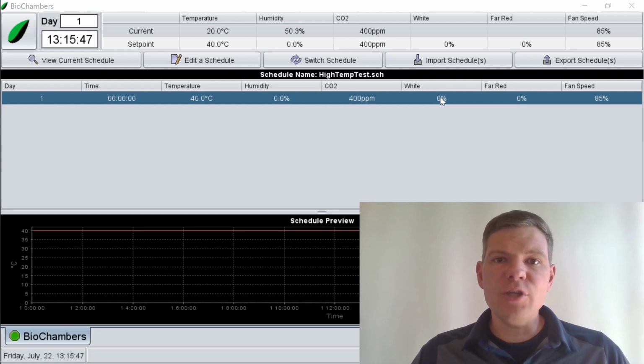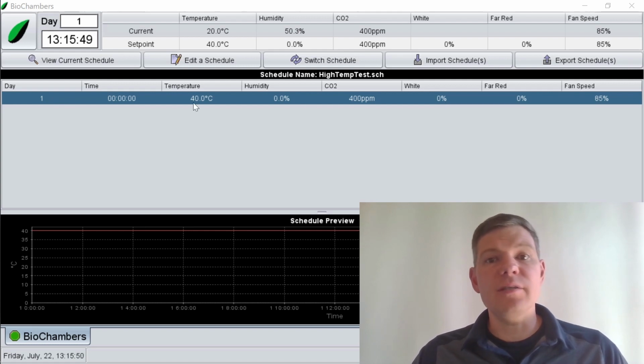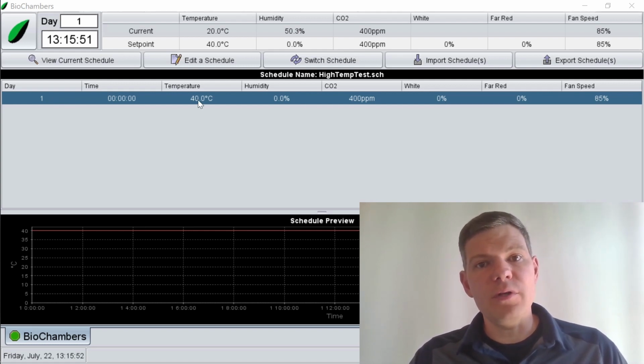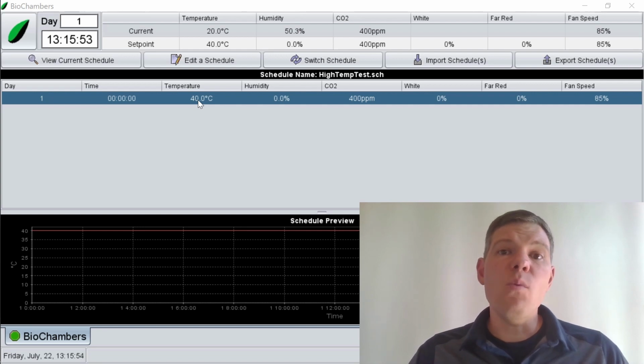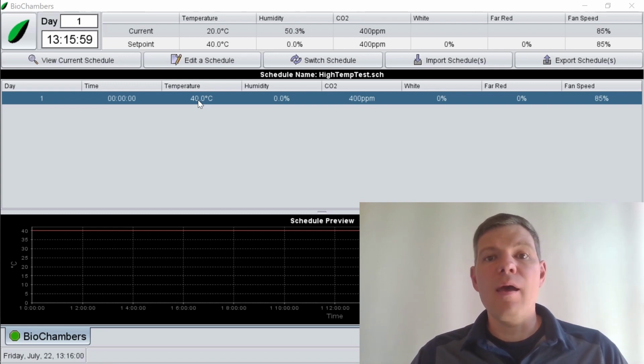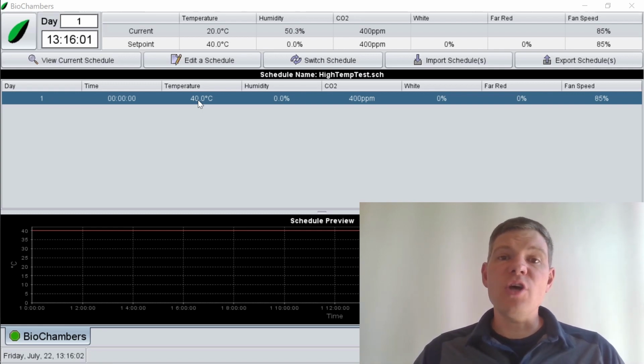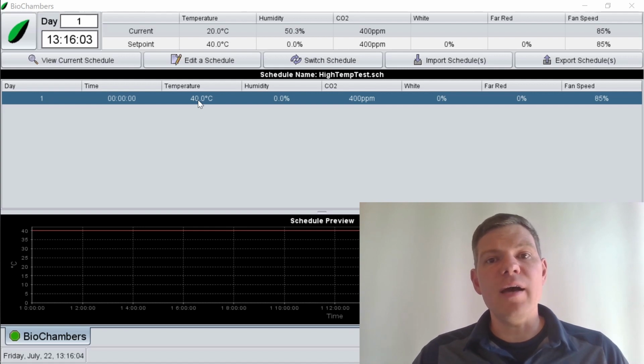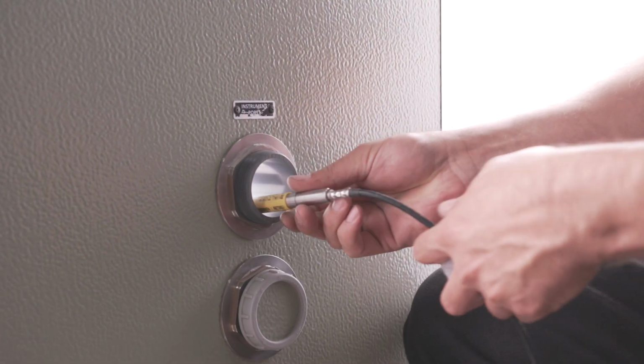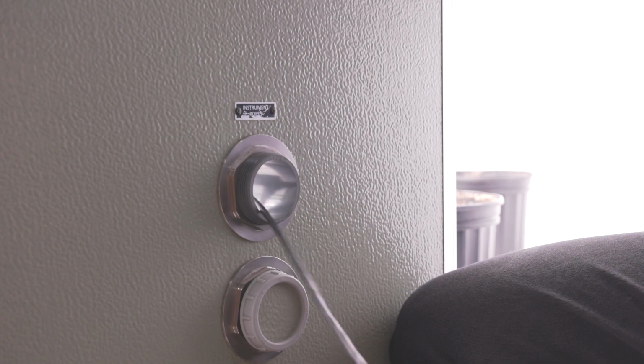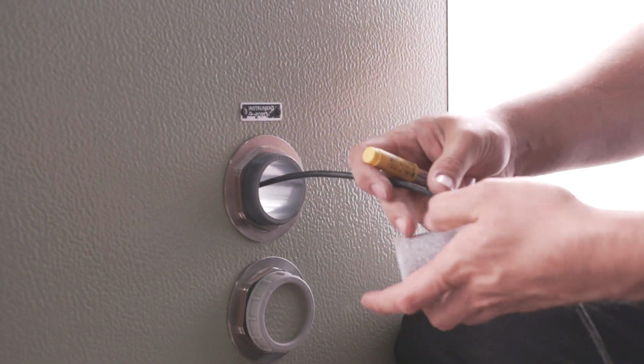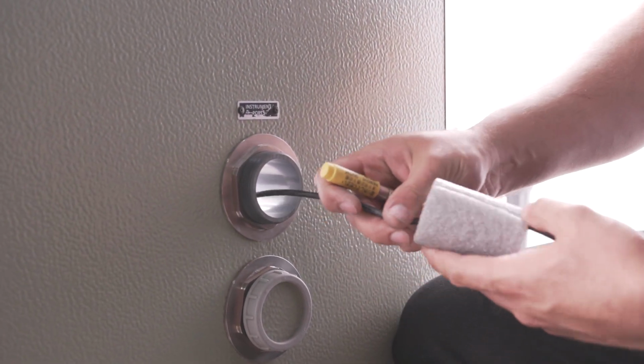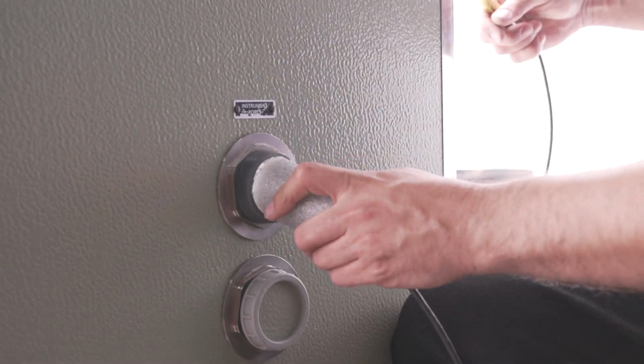Next, turn off the chamber lights and set your chamber to its highest achievable temperature, say 40 degrees. Then wait 15 minutes after the chamber has reached 40 degrees and until the sensor has reached stability. Again, closing the fresh air and exhaust dampers helps quickly achieve high temperatures. If the chamber setpoint sensor reads more than 1 degree differently than the recently calibrated sensor, contact us to have your chamber temperature sensor recalibrated or replaced.